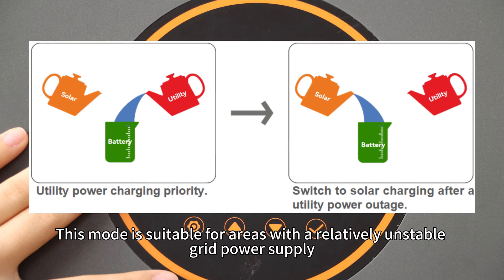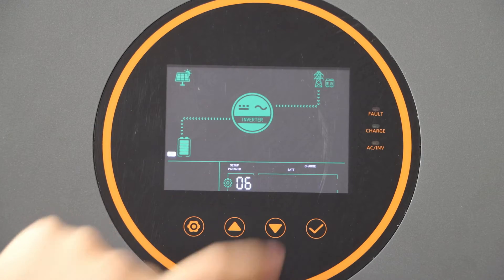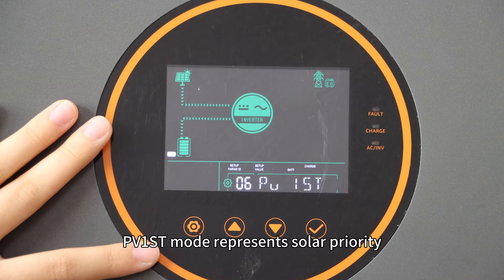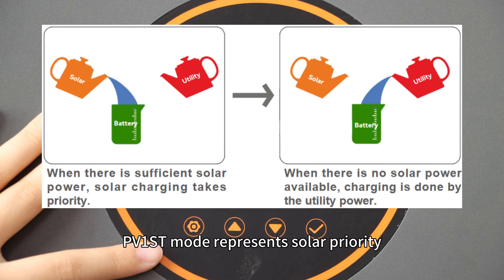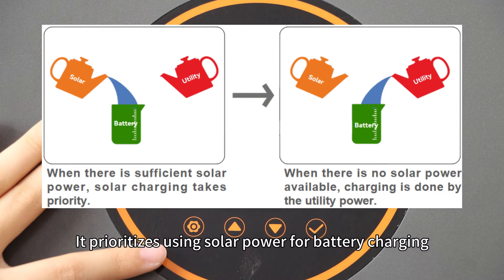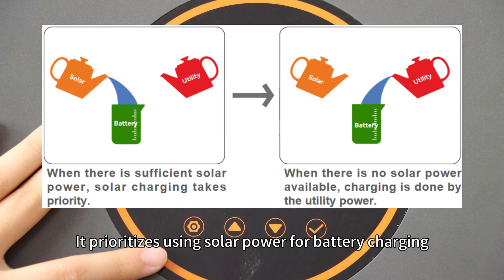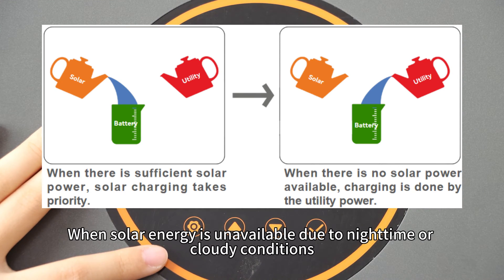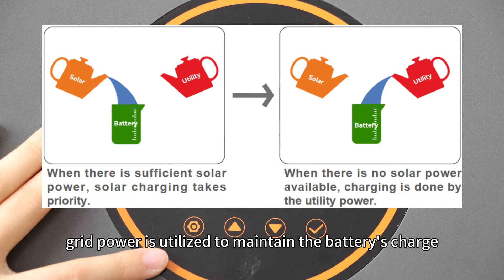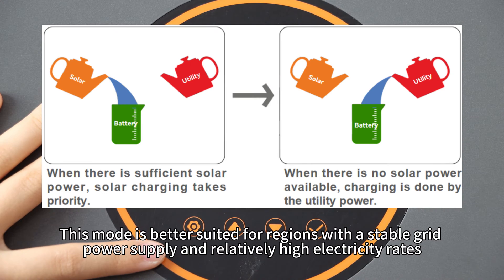This mode is suitable for areas with a relatively unstable grid power supply. PV-1ST mode represents the solar priority — it prioritizes using solar power for battery charging. When solar power is unavailable due to nighttime or cloudy conditions, grid power is utilized to maintain the battery's charge. This mode is better suited for regions with stable grid power supply and relatively high electricity rates.